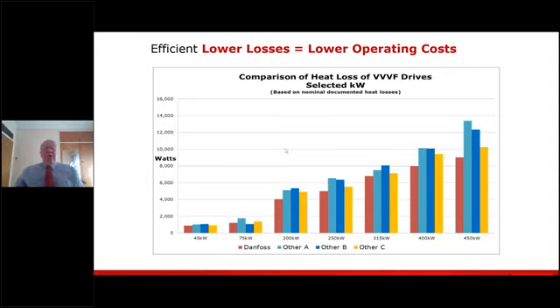So if we take a look at the graph, this is what I mean by saying that you can't put all drives in the same compartment, because you'll see that obviously we've got the Danfoss, and for reasons of ethics, I can't mention the other manufacturers' drives. But if one looks at the lower power range from 45 to 75 kilowatts, you'll see they're pretty much of a muchness, they're pretty much equal. However, when you start to get to the high power ratings, from 90 kilowatts upwards, you'll see that there are differences between all these drive manufacturers that I'm showing here.